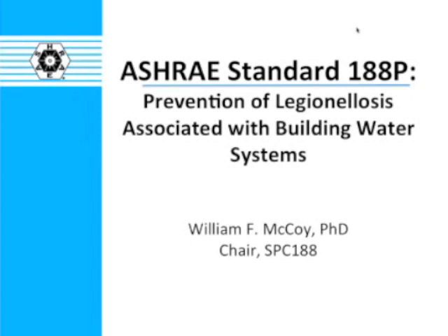than it solves. Added to that, Simon, in the States there are many excellent guidance documents which are publicly available to everyone. You mentioned one, the ASHRAE Guideline 12, 2000, but there are others that are widely available and used, in which specific recommendations are given for particular building water systems, for example in regard to temperature, or in regard to chlorine concentration or other oxidants. So what ASHRAE Standard 188 does is say, here's what you will do if you're going to comply with the standard. You will form a team and decide which hazard control is most appropriate for your building. And you will do that in accordance with this risk management process, and then you will validate and verify that it is working.